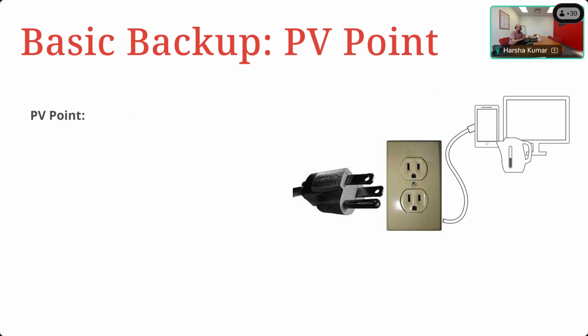With that in mind, we have this feature which we call the PV Point. The PV Point does not require batteries, and it's only 120 AC, not 240, so it's only line-neutral, not line-neutral-line. It is only active when hydro is down. So if it's daytime and hydro is down, you can get 120 AC continuous at 1.5 kilowatts, plus an inrush capacity of 2.5 kilowatts for 3 seconds.